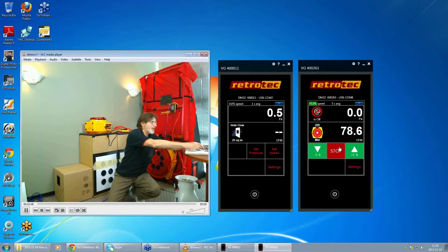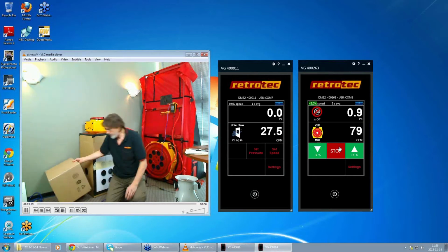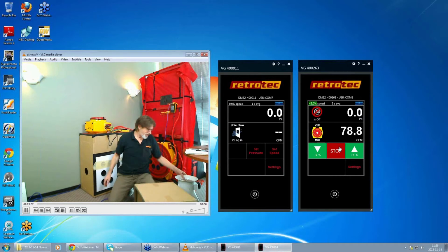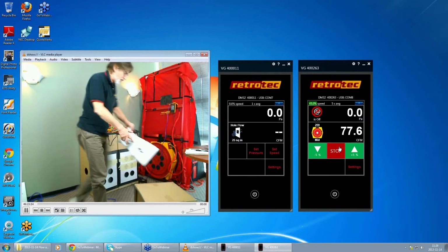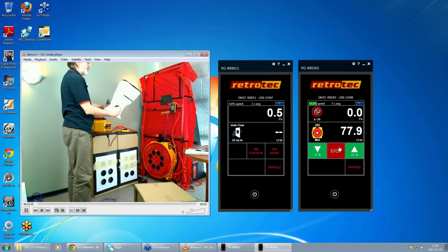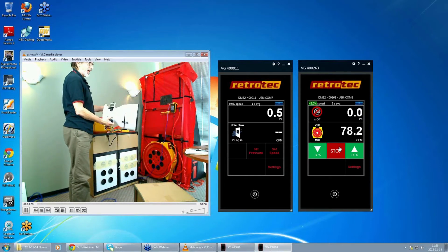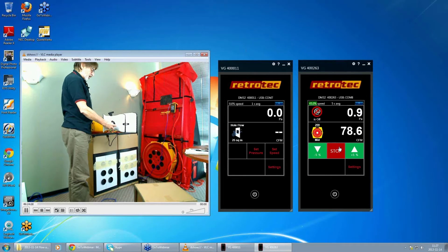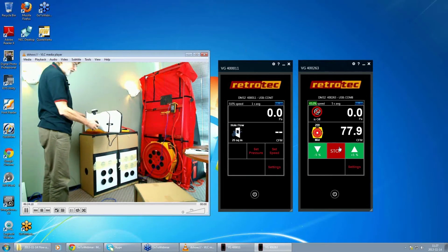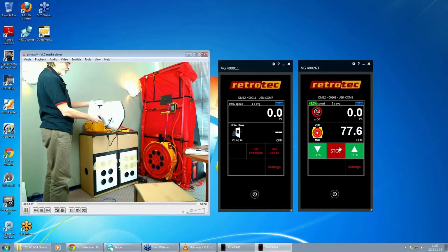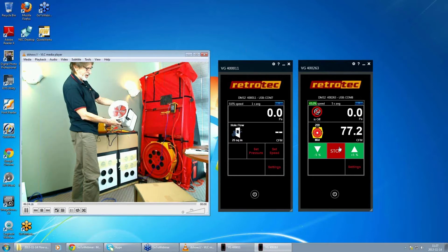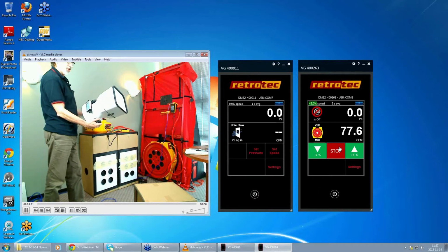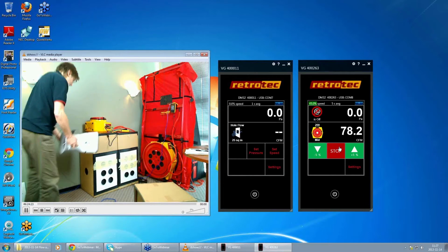So I'm going to try and measure that flow with a different type of device. This is called the Flow Finder, which is a new powered flow hood, which is a nice little device, and very, very sophisticated. And we'll see how it does in terms of measuring flow. So the first thing we're going to do is turn it on. And it's already set for CFM. And this is called a powered flow hood. So it has its own little fan in here that will run. It will get the pressure across this measurement hole to 0, so it's not going to influence the flow at all. And we'll see how it does.